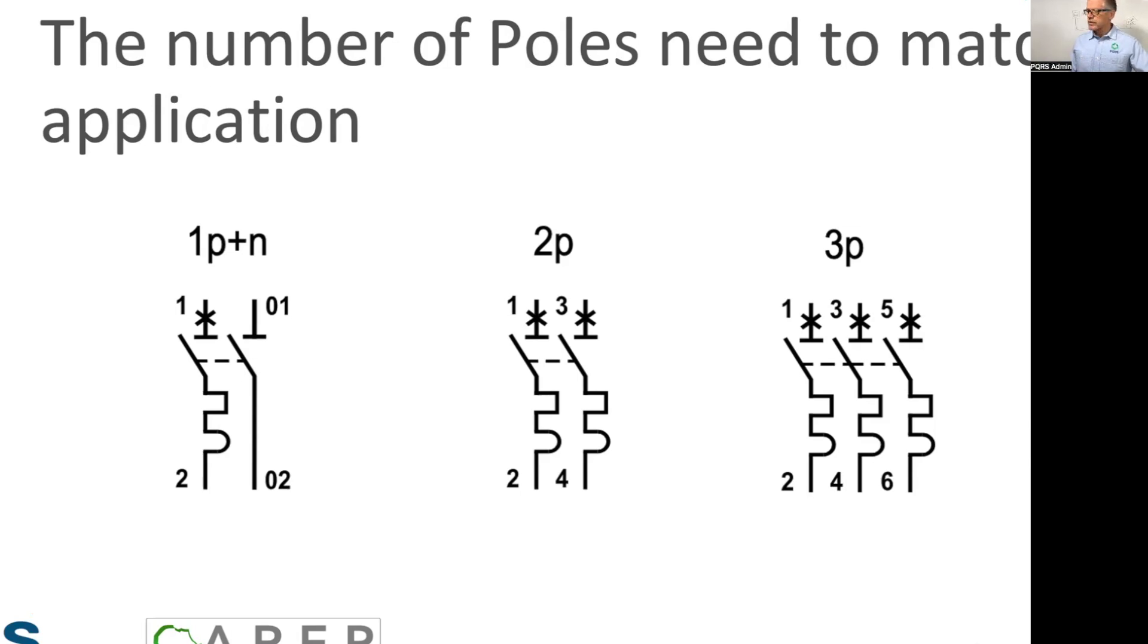But all this is telling us is that you would fit your live on 1 and 2, and you would fit your neutral on O1 and O2. The dash line in between means that the toggle is connected, and if the one trips, the other one is going to trip.